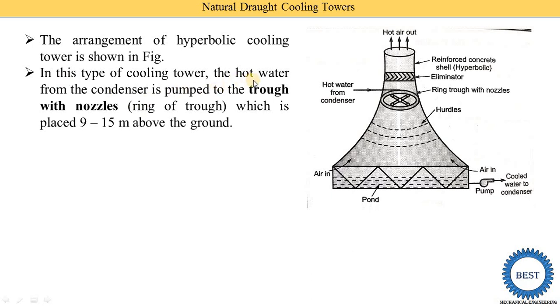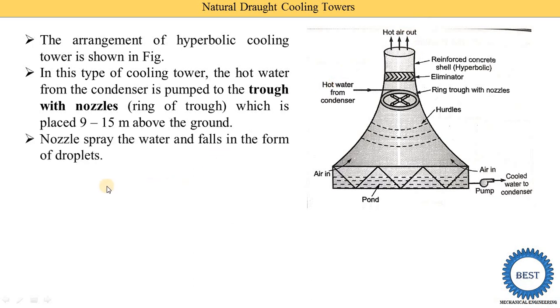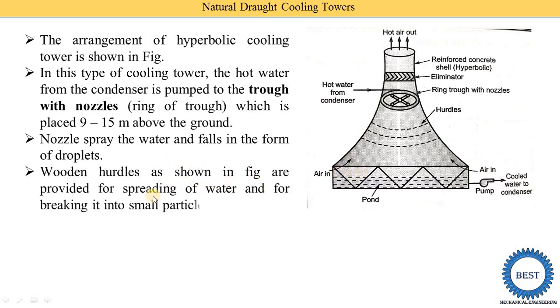In this type of cooling tower, hot water from the condenser is pumped to the trough with nozzles (ring of trough), which is placed 9 to 15 meters above the ground. Hot water from the condenser is supplied here and from the various nozzles the water falls downward. As the water falls, air comes into contact with it and absorbs heat energy, reducing the water temperature. Cool water is collected at the base. Nozzles spread the water in the form of droplets, not jets. Wooden hurdles are provided for spreading the water and breaking it into small particles.